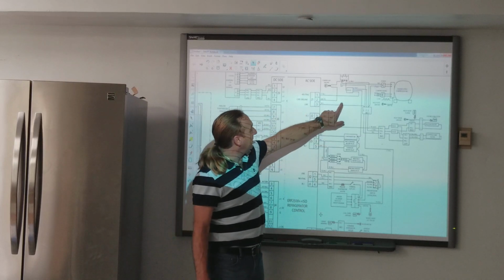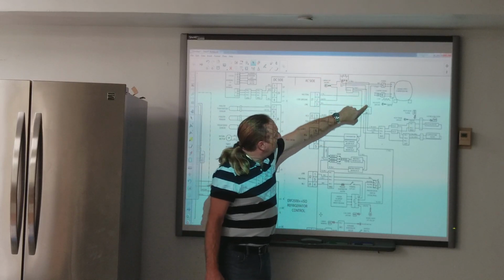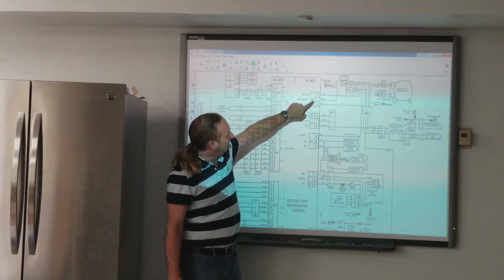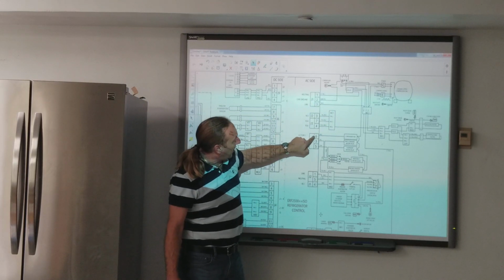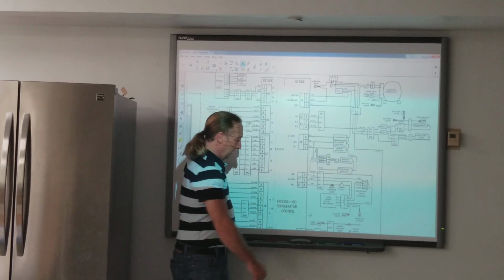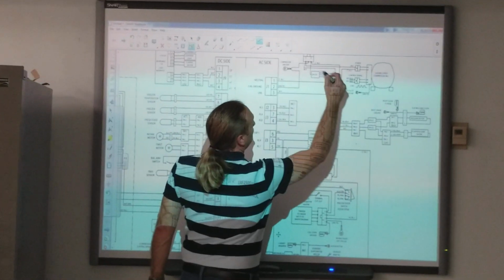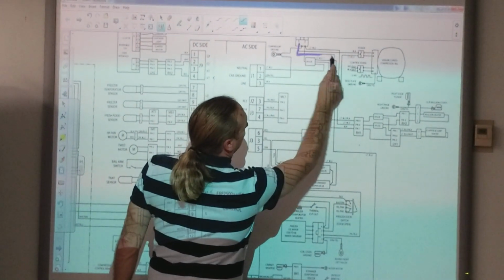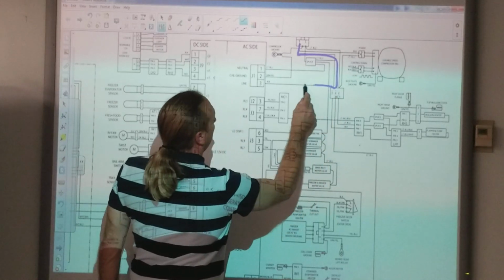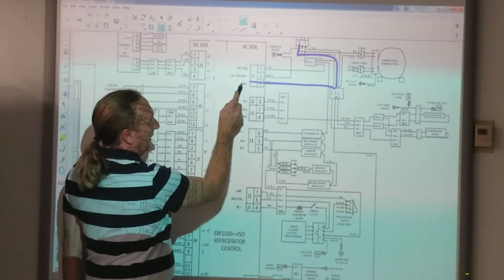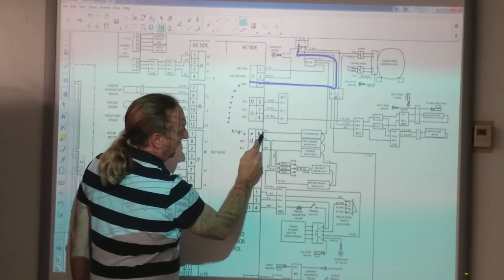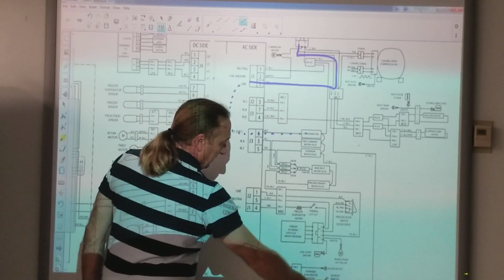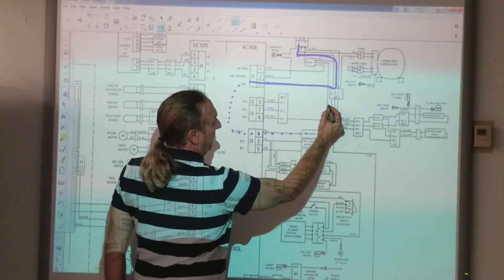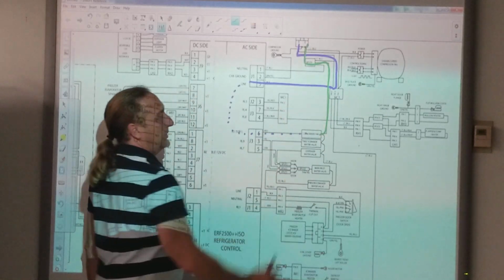Usually line one comes in, goes into black here, and the board sends power back out. Let's say this is line one, it comes into the board, then the board sends it to the condenser fan, and when it hits the condenser fan, it comes back out as neutral and goes back to the plug.